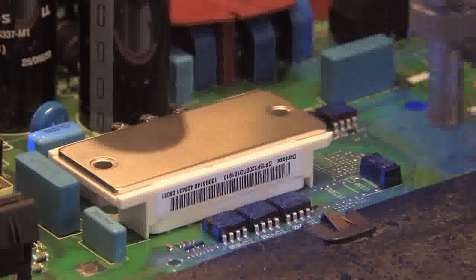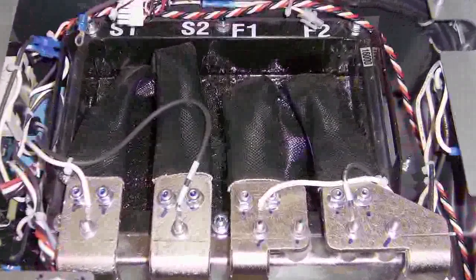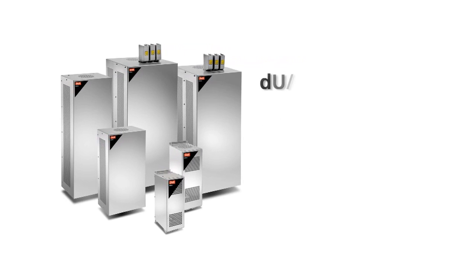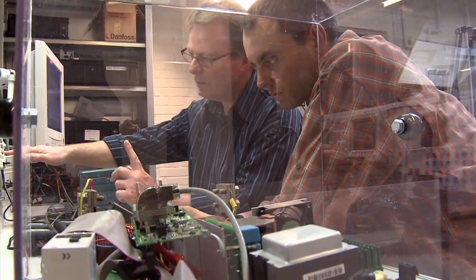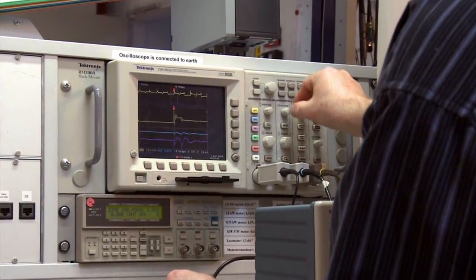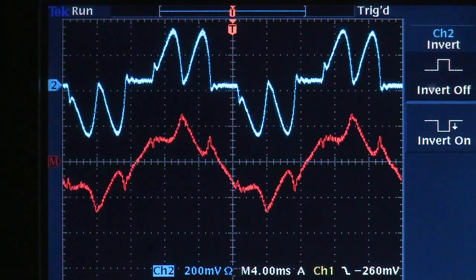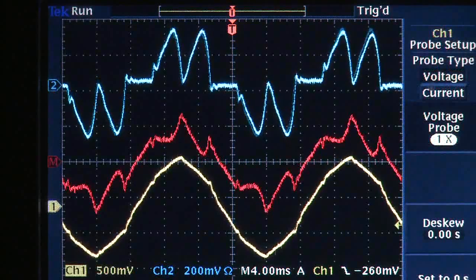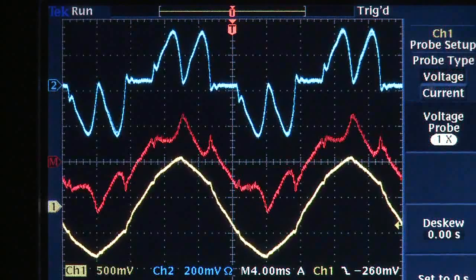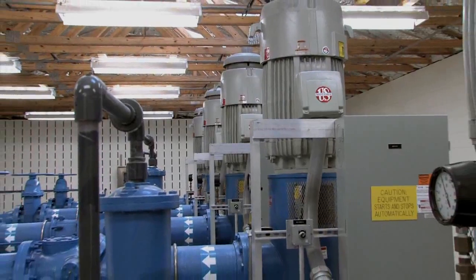VLT drives offer value with standard features like built-in DC coils. For sensitive applications, Danfoss offers dU/dt filters, sine wave filters and advanced harmonic filters. To eliminate harmonic distortions of the supply grid, Danfoss uses VLT drive technology to add and subtract power to the grid in exactly the same pattern as actual disturbances, but in counter-phase. This solution also raises the power factor from about 0.85 to 1, making Danfoss solutions technically and economically attractive.